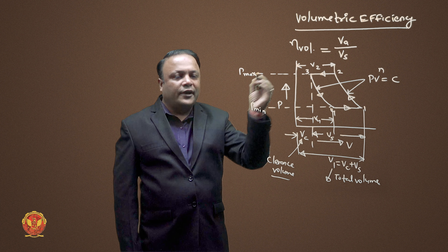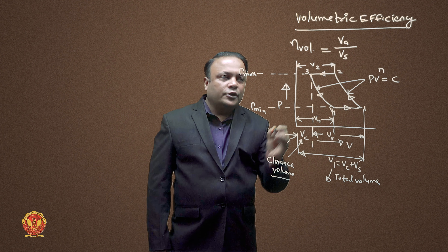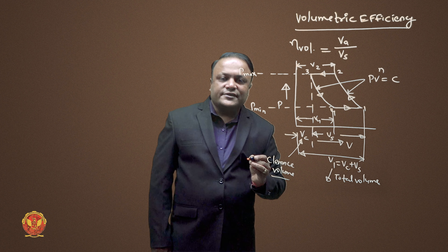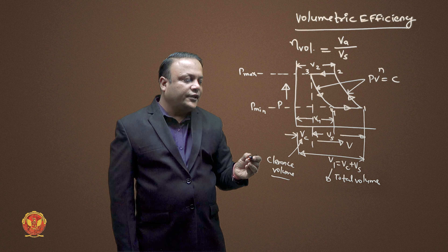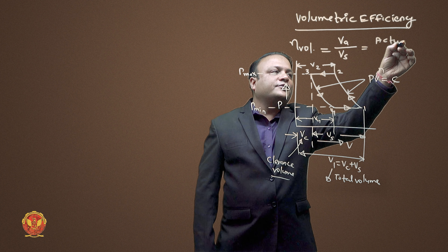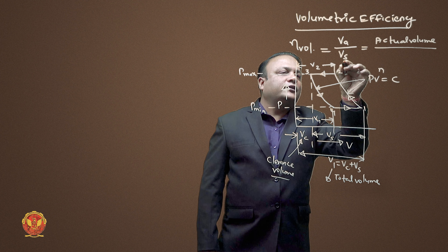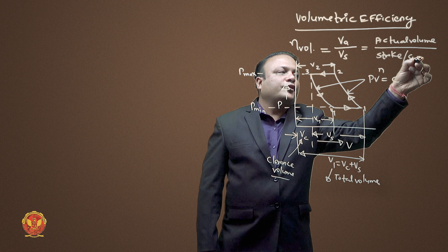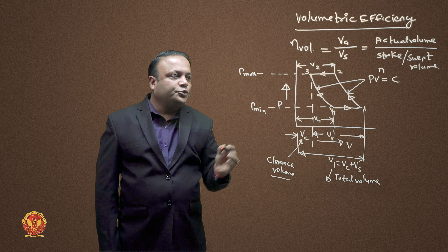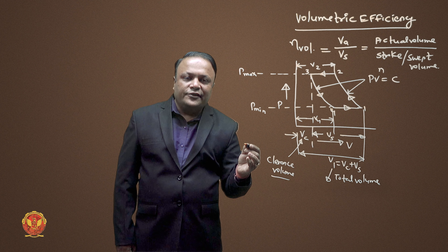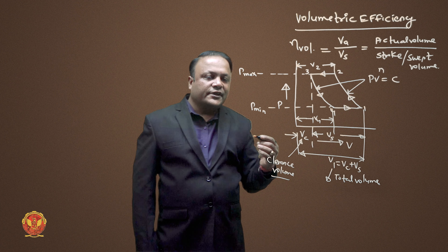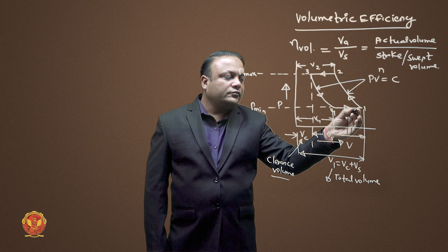After delivery, there is the clearance space, then polytropic expansion from 3 to 4, followed by suction — and this way the cycle continues. The actual volume corresponds to what is available at point V1 minus V4, and the stroke or swept volume VS is the theoretical volume. We talk about atmospheric conditions and how much volume, pressure, and temperature we had before compression.